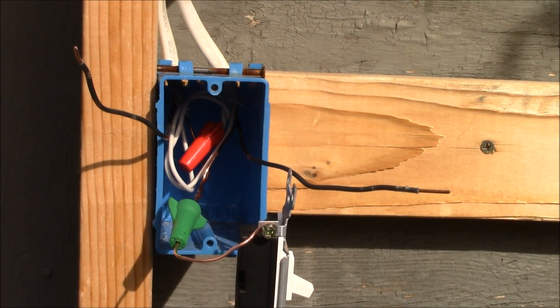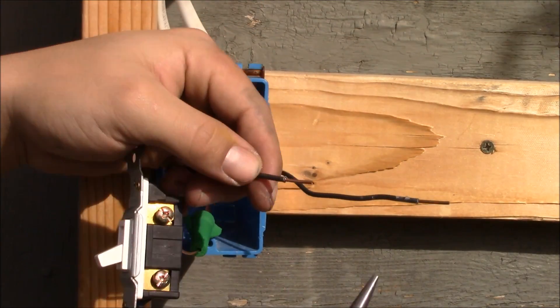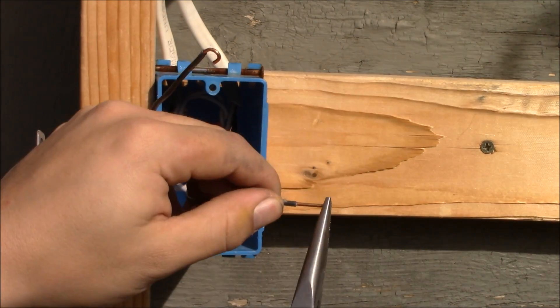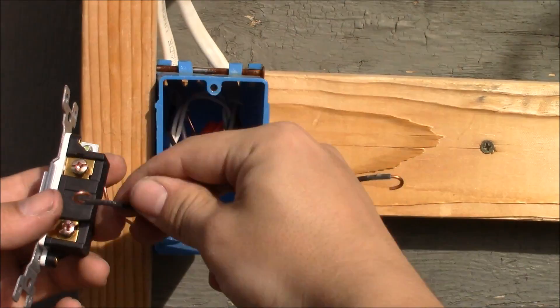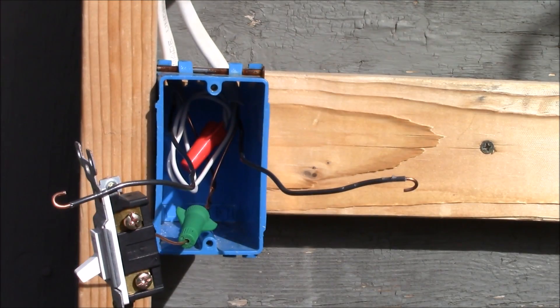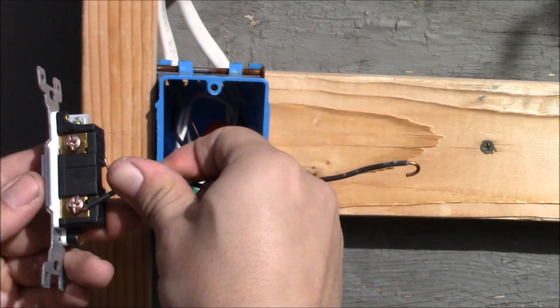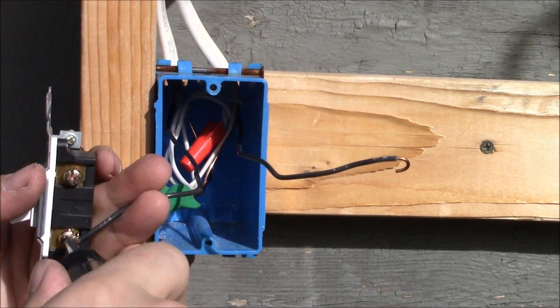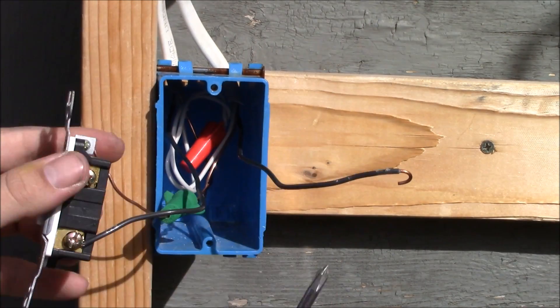Now it's time for the black hot conductors. We have the line wire, which is the wire bringing electrical energy into the system, and the load wire, which is the wire bringing energy to the light. We'll place the line wire on one bronze terminal in a clockwise manner, crimp it, and tighten it down securely.